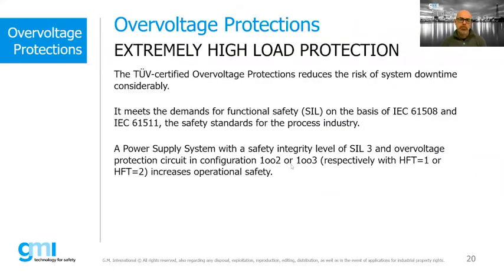Overvoltage protection, as mentioned above, is fundamental in a safety power supply system, because it allows us to reduce the risk of system downtime considerably. In fact, if one of the safety power supplies fails in an overvoltage condition, the protection brings the output to 0 volts, allowing the other safety power supply to continue working correctly without the risk of sending the system to shutdown. A standard power supply without protection would cause a shutdown of the whole plant, with the consequent repercussions on productivity and costs. A SIL3 level power supply system with overvoltage protection is able to increase operational safety and productivity, and reduce costs.